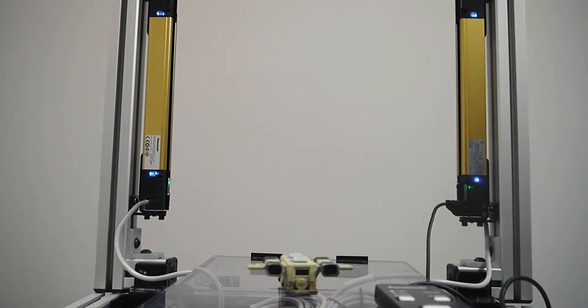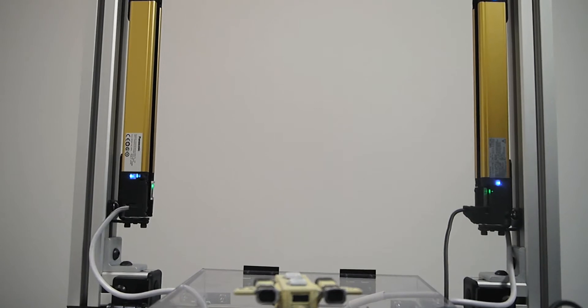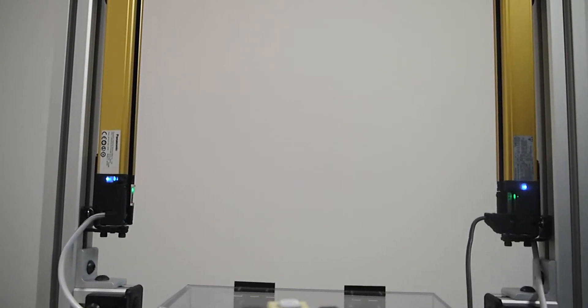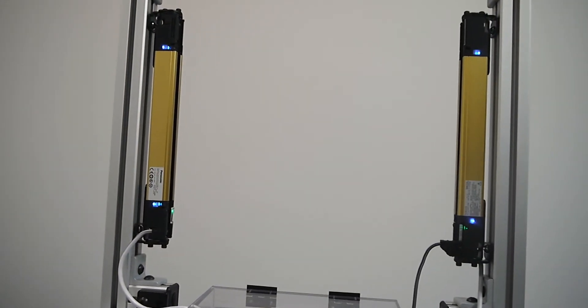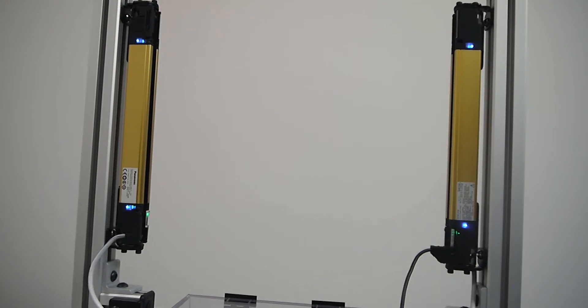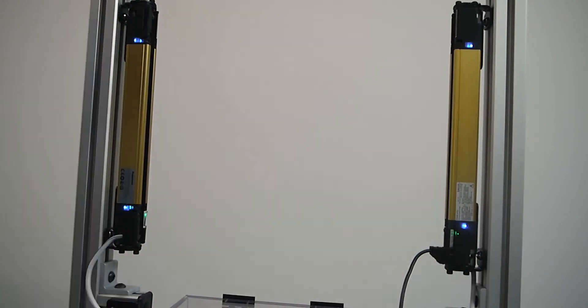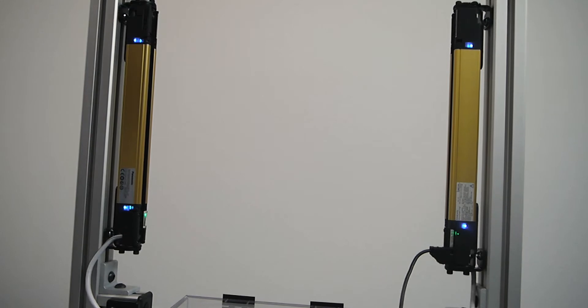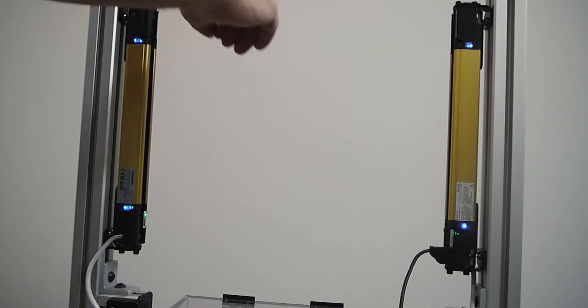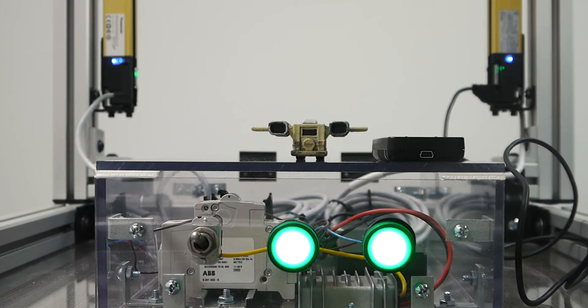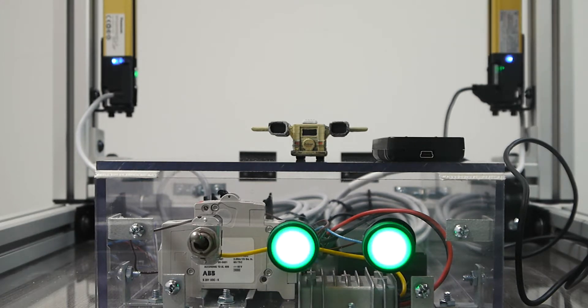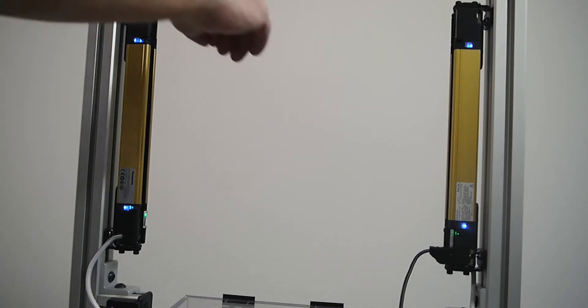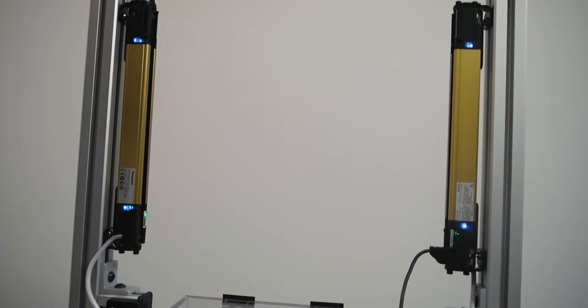Say you have an application where you are unspooling or spooling a metal coil that will be passing anywhere through the active area of the light curtain. You want the light curtain to ignore that coil, but you would want it to detect if the operator accidentally moved their hands into the active area of the sensor. Floating blanking windows is one way to potentially solve this application.